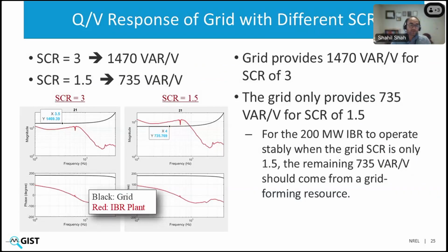So with that background on the Q by V scan, let me go back to our 200 megawatt plant, which was becoming unstable when the SCR was less than 3. So for an SCR of 3, for 200 megawatt base power and 500 kV base voltage, you can translate its Q by V response to 1470 VAR per volt.